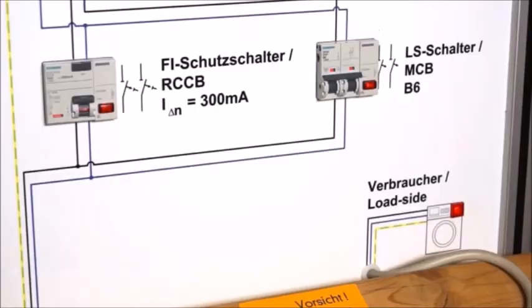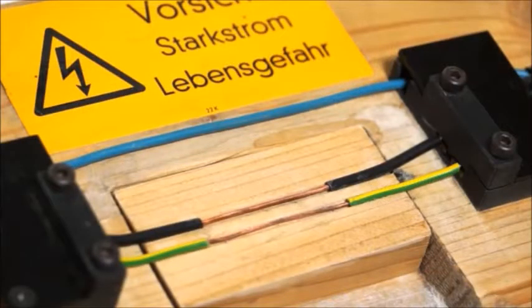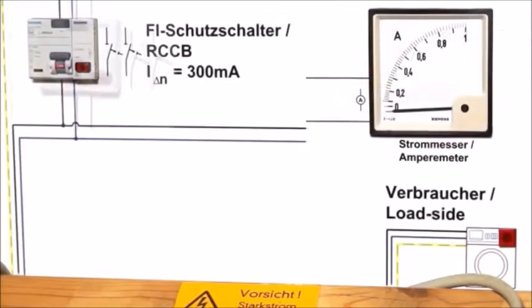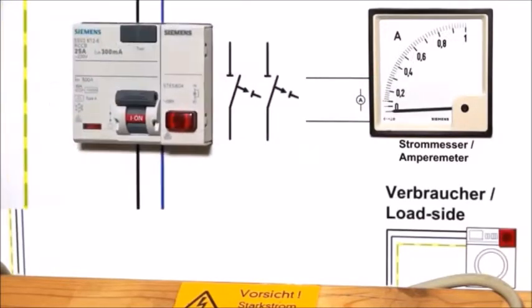This simulation shows how RCCBs can be used to provide fire protection. For this, the rated residual current must not exceed 300 milliampere. Our example shows an insulation fault between two cables. The applied voltage causes a current to flow across the fault location. A slight rise in the fault current is sufficient for the RCCB's tripping. This prevents the formation of fire.